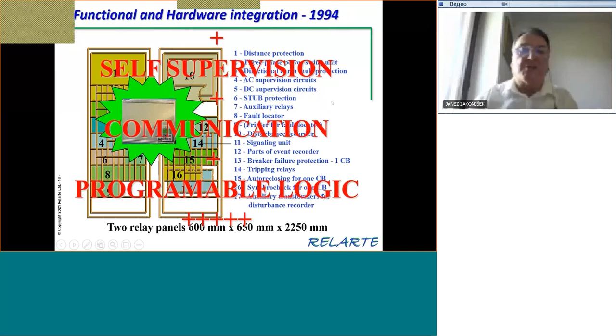If you look at today, we have the possibility to be connected to all relays within the system, all IEDs, and if something happens in the system, one fault, it is possible to download all disturbance recorder data, not only from the relay which should operate, but from all relays around. On this basis, it is necessary to determine whether they operated correctly or not, and conclude whether it's necessary to test them. I know that in Russia, for example, there is one provider which can provide such systems, and I think that is very positive.